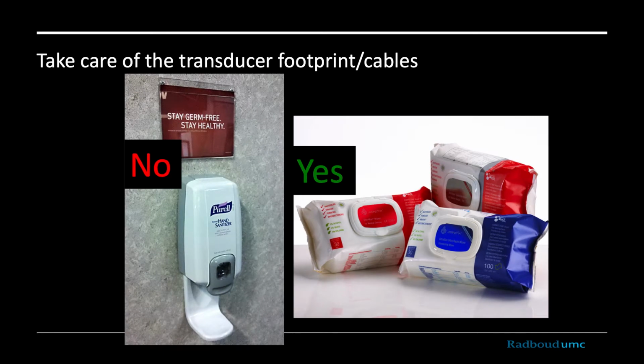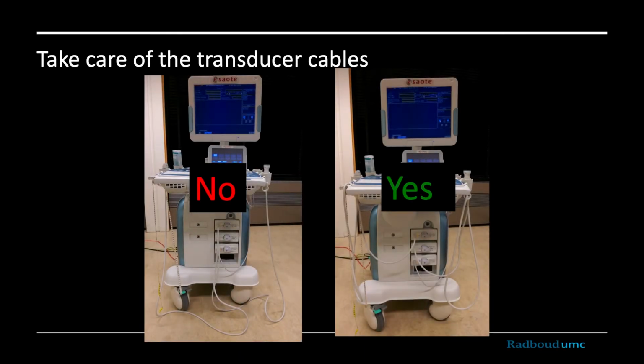As a further tip, it is good practice to take good care of your transducer or probe footprint and cables. Please do not use alcohol-based solutions for this, as the rubber surfaces and casings will degrade. There are these special wipes for medical equipment that are usually very handy to clean your ultrasound machine before or after you scan a patient. Check your local hygiene department and the equipment manufacturer to see which solution suits you best. Finally, I can recommend to also take good care of the transducer cables. They are like the optic nerves of your probe, and if you drive over them or tie a knot into them, they will slowly go blind, degrading the image on the screen. So put them up and tuck them away in the hooks that are attached to the machine, so the wheels will not drive over them, and your equipment will be good to go for a very long time.